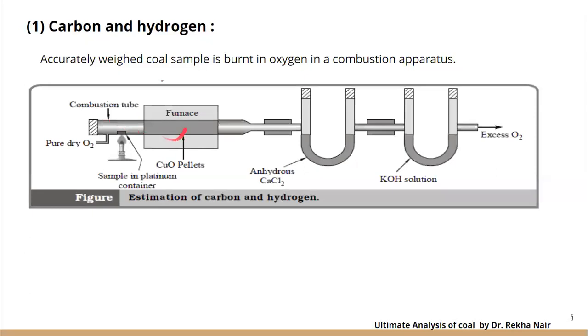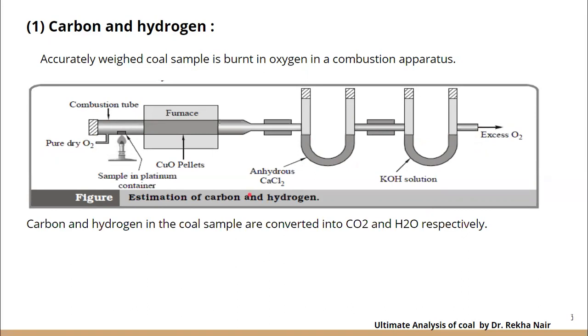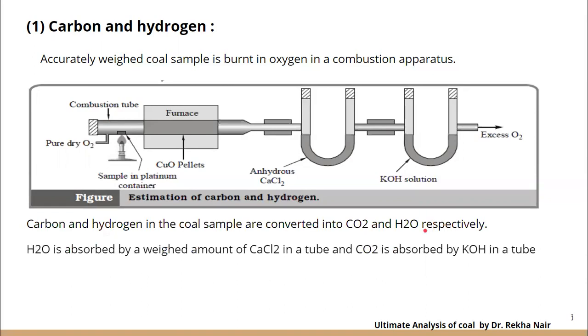This is the combustion tube. This is the furnace. Here we are sending the amount of oxygen required for combustion. Here we have a U-tube containing anhydrous calcium chloride, and here we have another U-tube containing KOH solution. The excess amount of oxygen not used during combustion will be removed from here. Carbon and hydrogen in the coal sample will be converted into carbon dioxide and water respectively — carbon reacts with oxygen to form CO2, and hydrogen reacts with oxygen to form water.